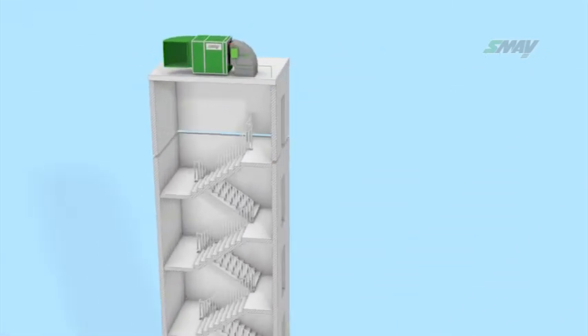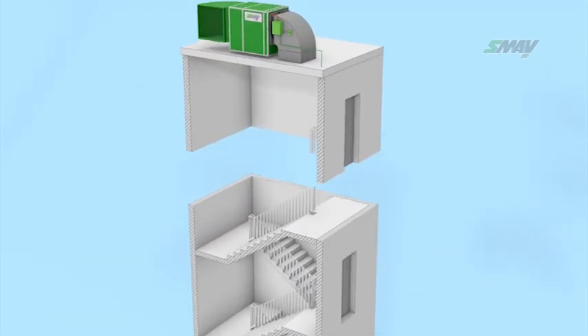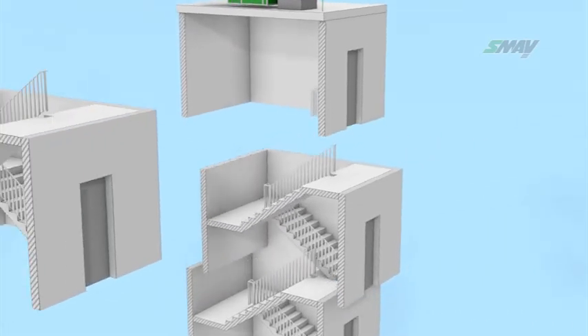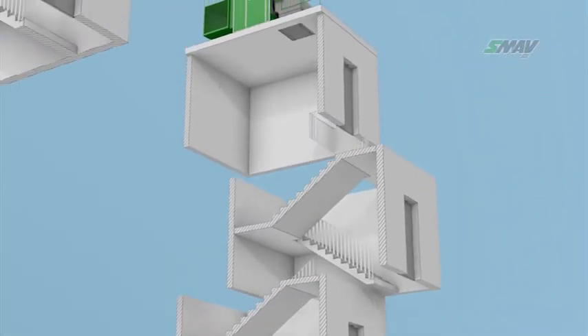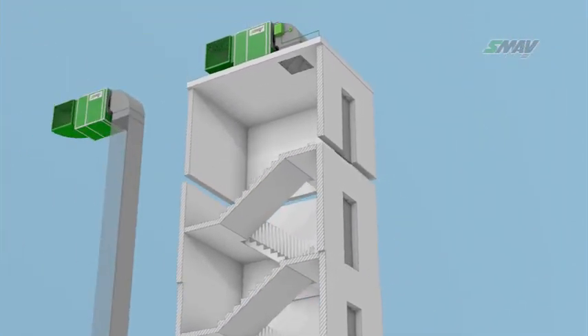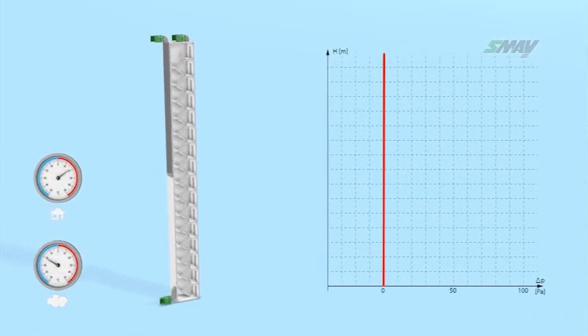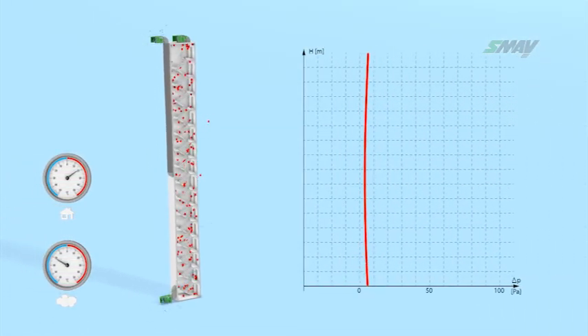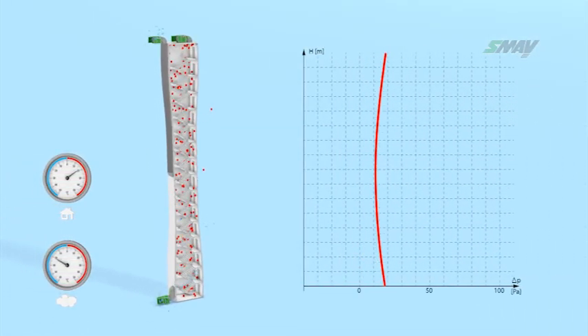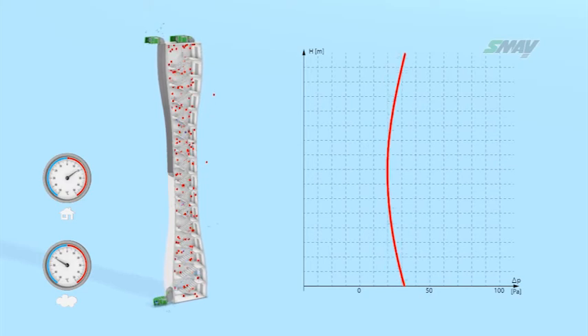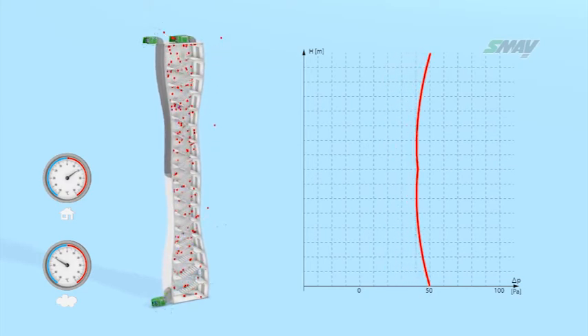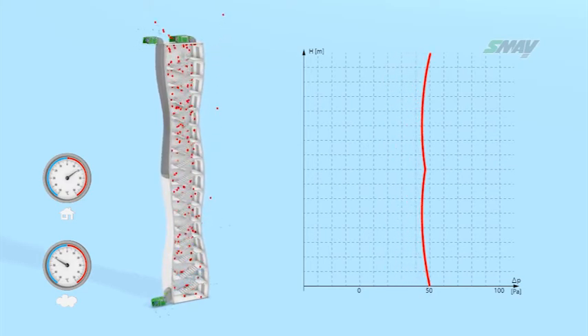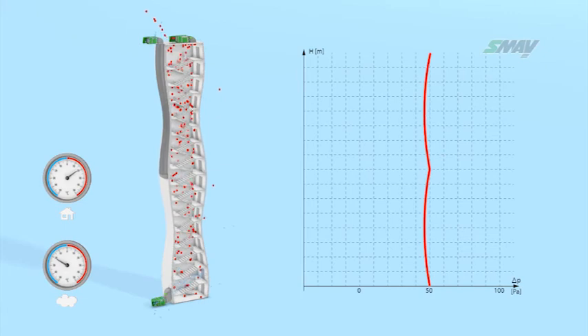For stairwells in buildings which are more than 35 meters tall, an additional air supply point is required every 10 floors. The air supply to the stairwell is activated automatically once pressure drops below a preset value, which may be caused by leaks and opened emergency exits.